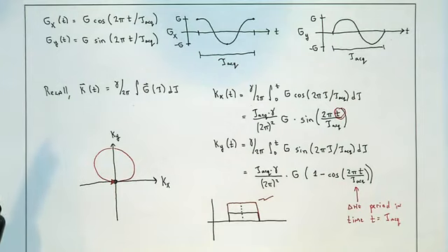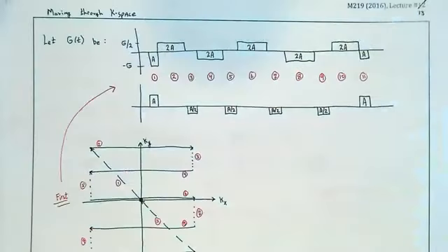Yep. When you ask how much gradient has to be applied while we prepare the lines, you're talking about net gradients. If you apply 2A positive and 2A negative, the net is zero. Yep. And so we saw that in this example here.